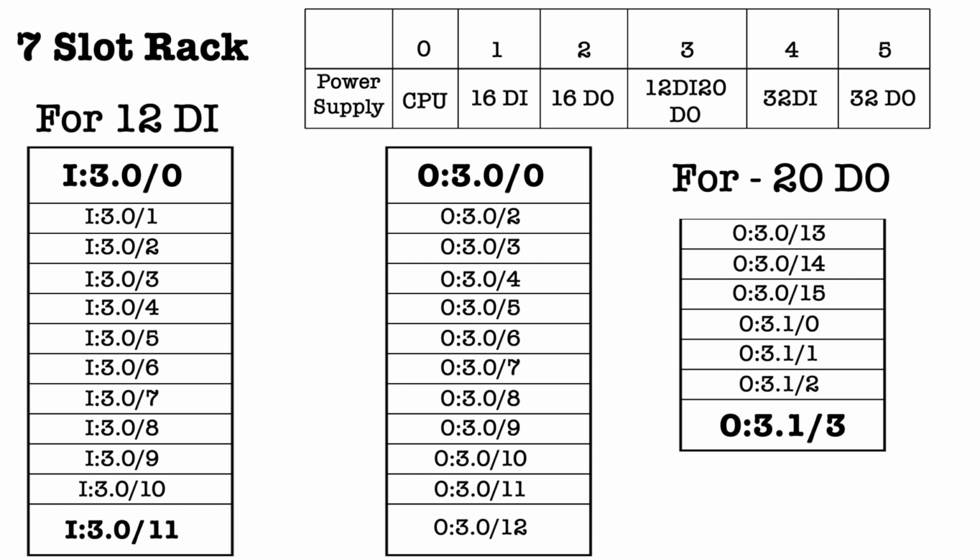So in total this covers our 20 digital output addressing, which starts from O:3.0/0 and ends at O:3.1/3. Since in a word we only have 16 bits, to cover the 4 remaining bits for 20 digital outputs, we have to take the second word, and take 4 bits of it. Okay, I think this is clear to you.